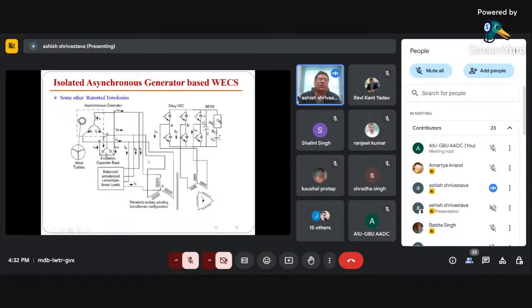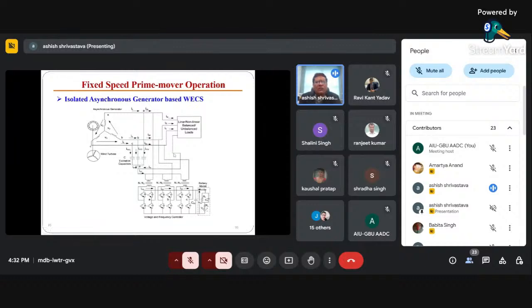Voltage is being injected according to the load requirement and the reactive power compensation requirement. Similarly, you have a transformer in all three phases, and depending upon the N1 N2 turns ratio you can inject. If you are charging the battery, power flow will be on this side. If you are making reactive power compensation from this side, power will feed back to this side. So power flow can take place on both sides.